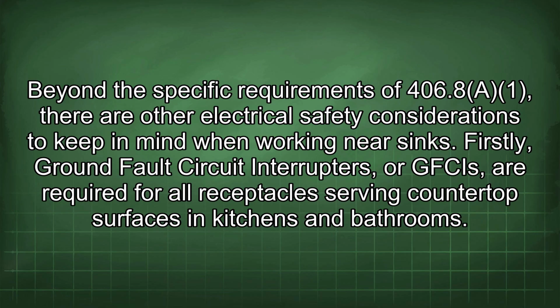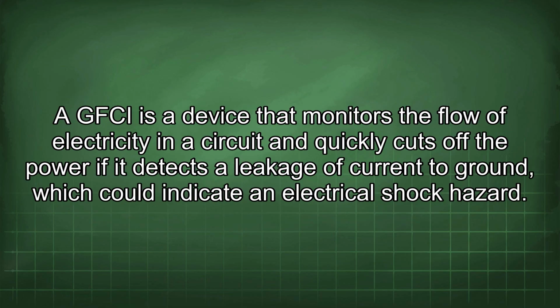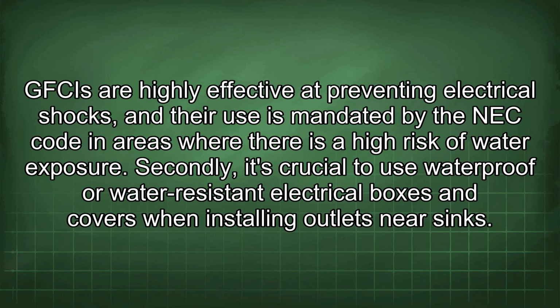Beyond the specific requirements of 406.8(A)(1), there are other electrical safety considerations to keep in mind when working near sinks. Firstly, ground fault circuit interrupters, or GFCIs, are required for all receptacles serving countertop surfaces in kitchens and bathrooms. A GFCI is a device that monitors the flow of electricity in a circuit and quickly cuts off the power if it detects a leakage of current to ground, which could indicate an electrical shock hazard. GFCIs are highly effective at preventing electrical shocks, and their use is mandated by the NEC code in areas where there is a high risk of water exposure.